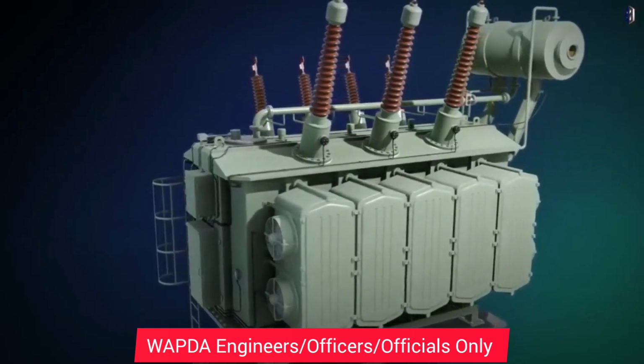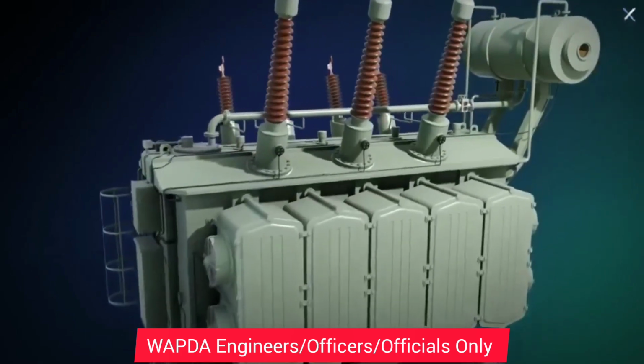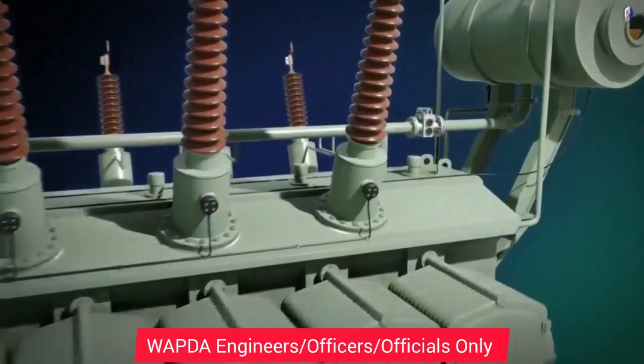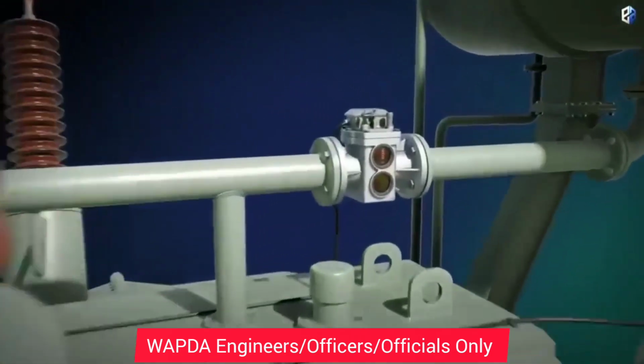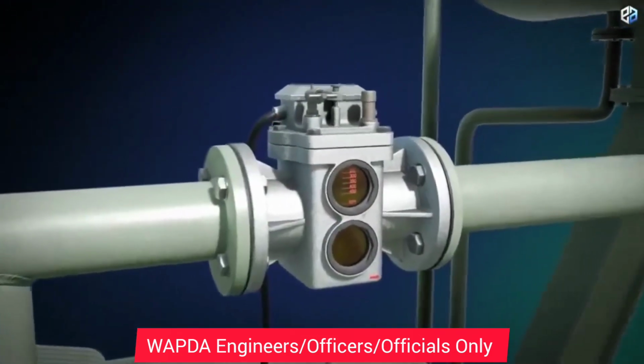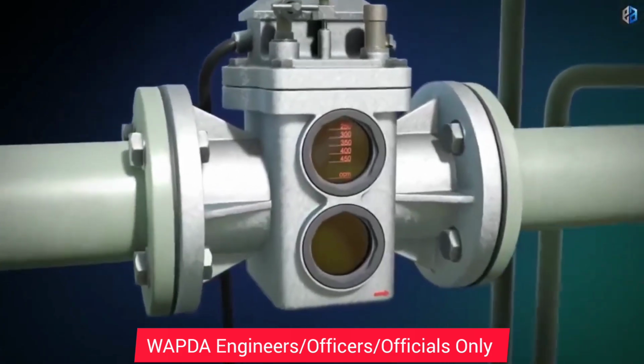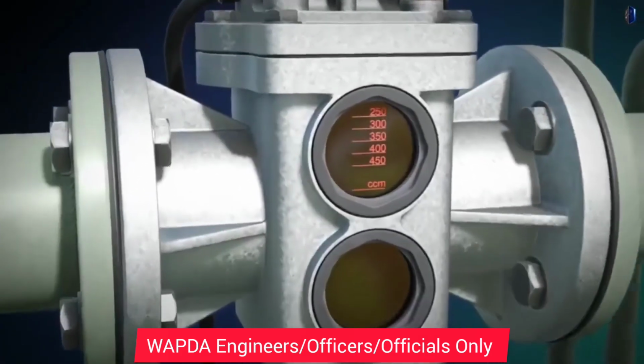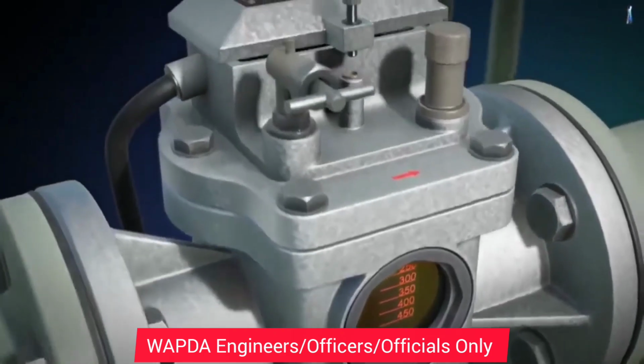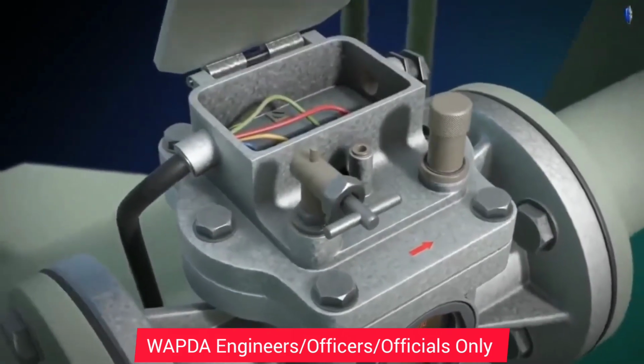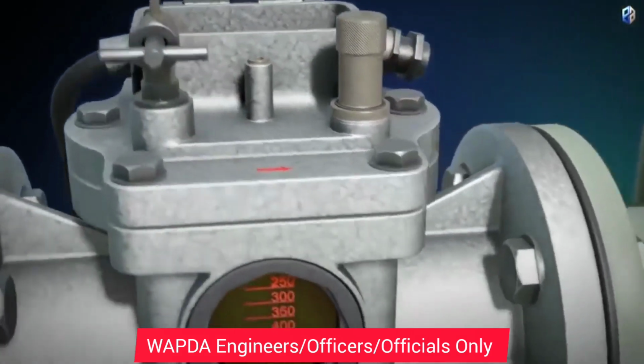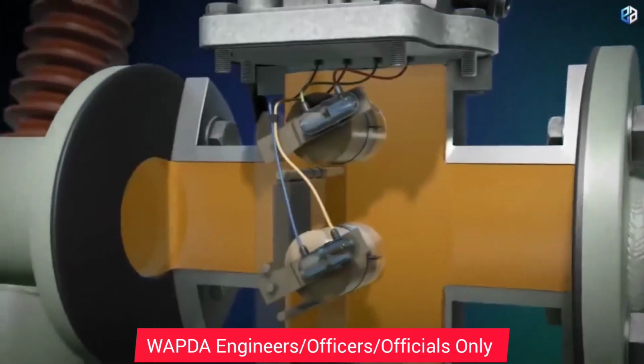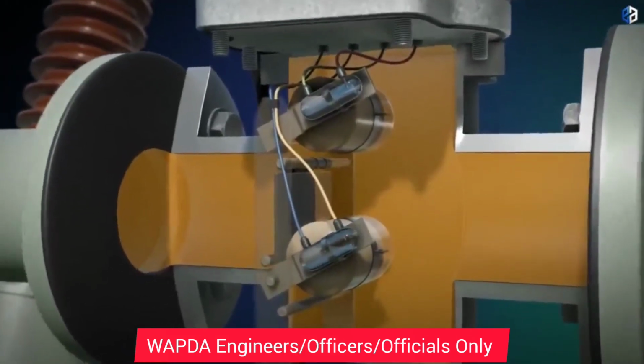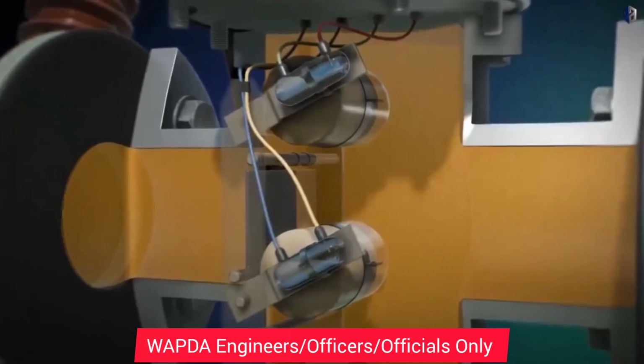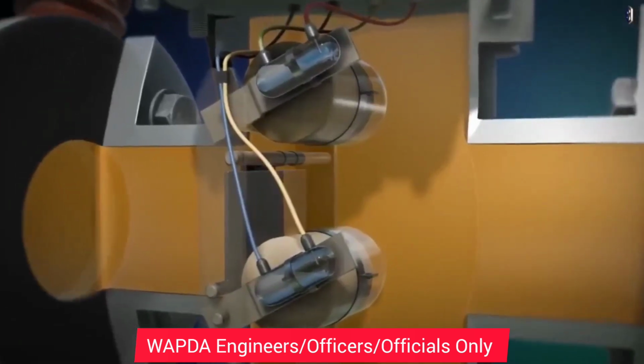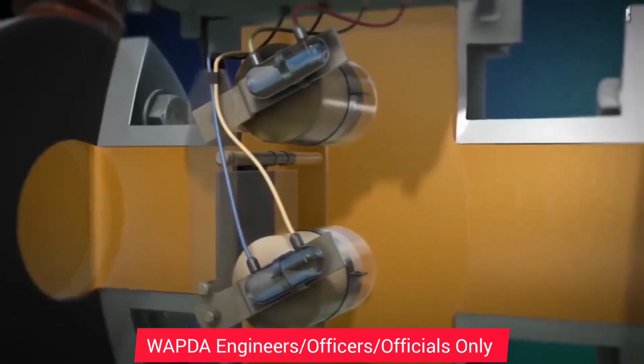Here we see our oil-cooled power transformer. The Buchholz relay is located in the pipe between the main transformer boiler and the oil expansion tank. Here you can first see the housing, which is usually equipped with two switching contacts inside and a terminal box on the top. The housing of the Buchholz relay is completely filled with transformer oil. There are two floats inside, similar to a water level regulator, one at the top, one at the bottom, which today are often designed with magnetic or reed switches.